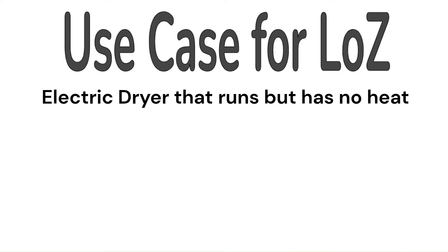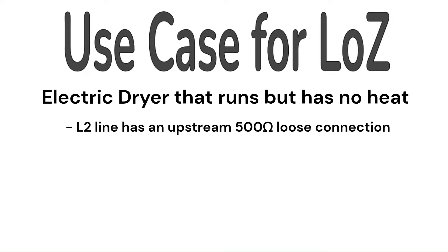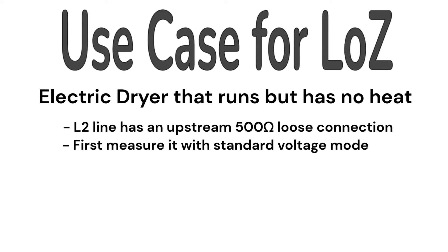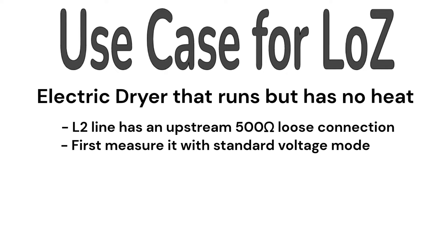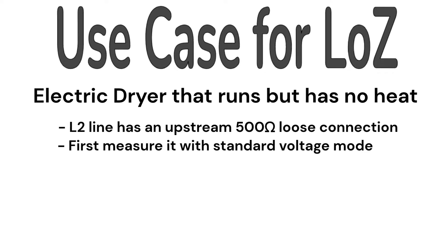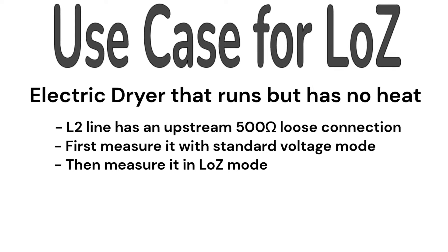Here's the use case for low Z. We have an electric dryer that runs, but has no heat. The L2 voltage line has a loose connection in an upstream junction box, in the order of about 500 ohms. We first measure it using the standard AC voltage mode, and then use the low Z mode to measure it.